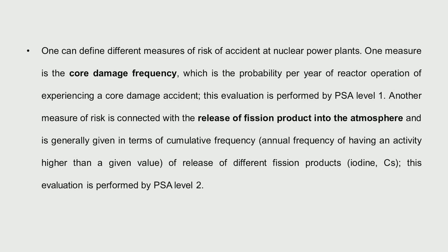Once you know that, you start thinking about what happens next: what are the consequences? Having the core been damaged, these fission products can come to the containment environment or to the outer environment. So the next measure is how much of this fission product will come to the atmosphere and what is the probability — that comes under PSA Level 2, where we are mainly worried about fission products such as iodine and cesium.